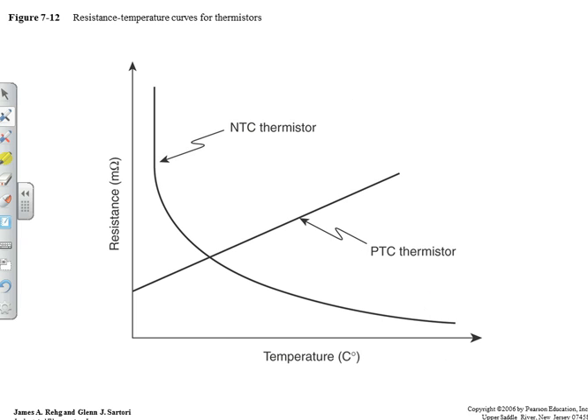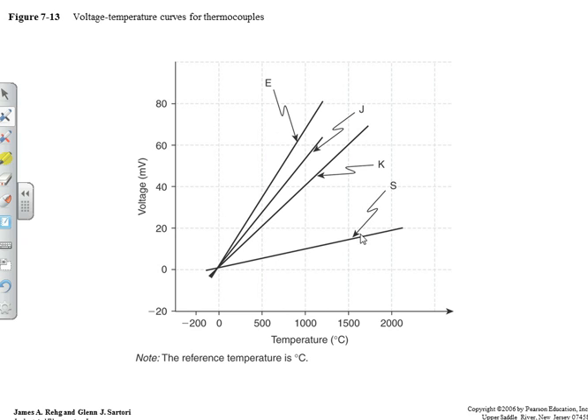Your resistance temperature devices have curves associated with them. So when I look to see how the ohms change per degree, I'm going to have to find the curve of the instrument I'm working on, whether it's already installed and hooked up to my meter or not, either case could apply. But I have different types, so depending on what I make the material out of, I have S, J, K, and E type temperature.